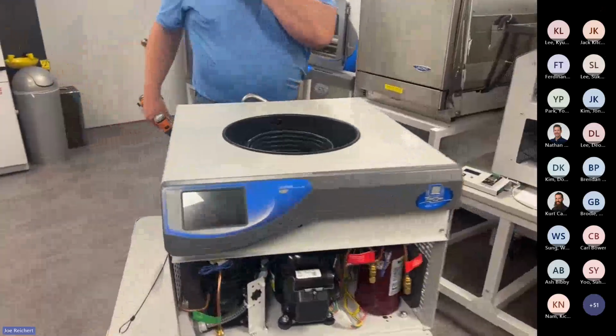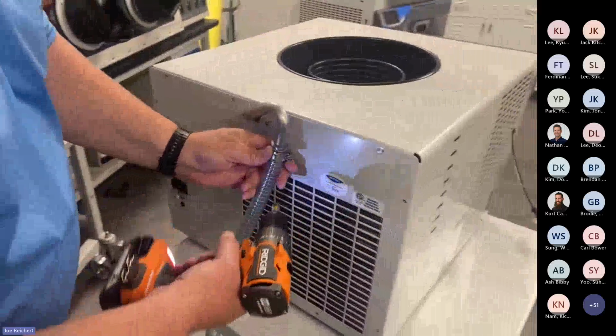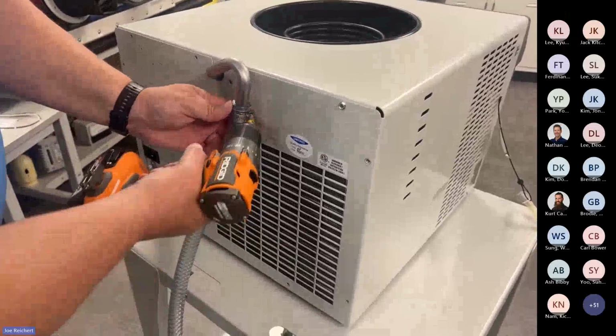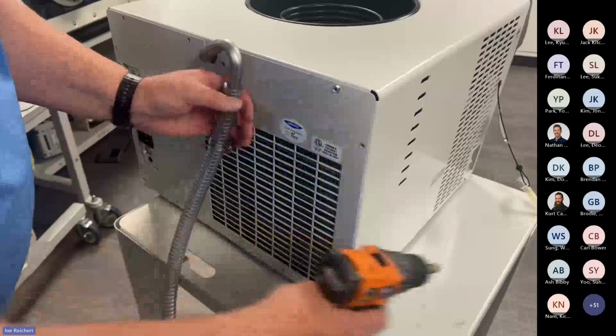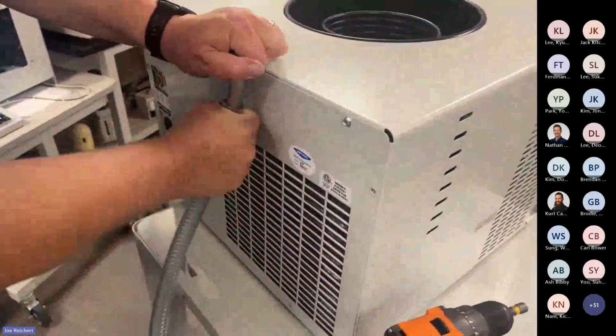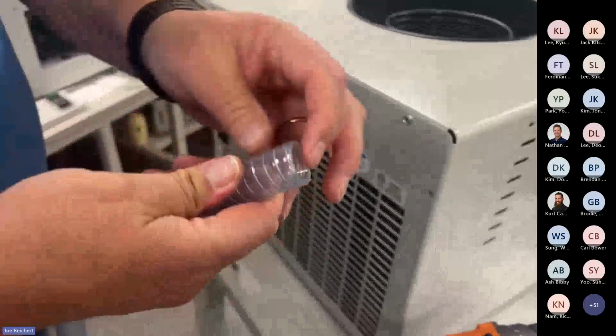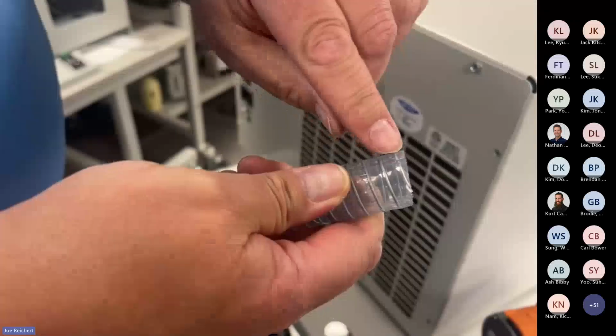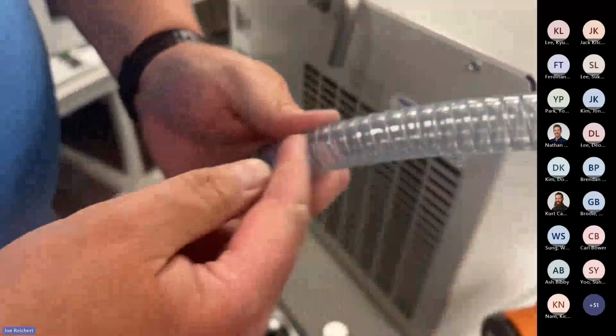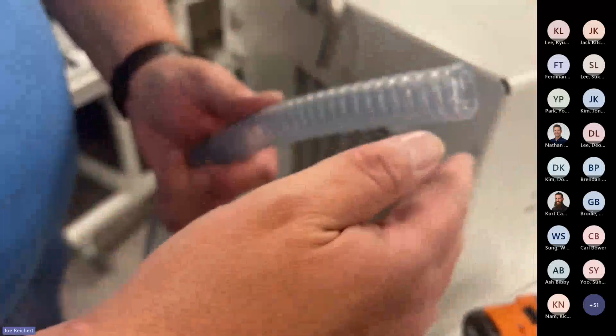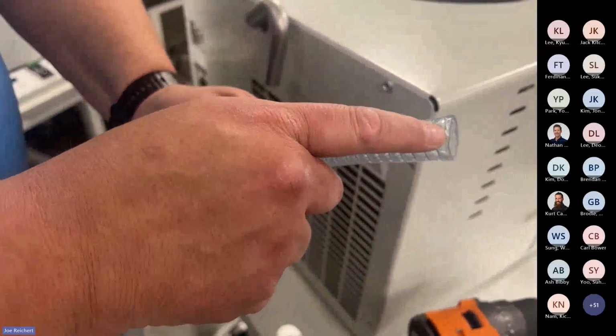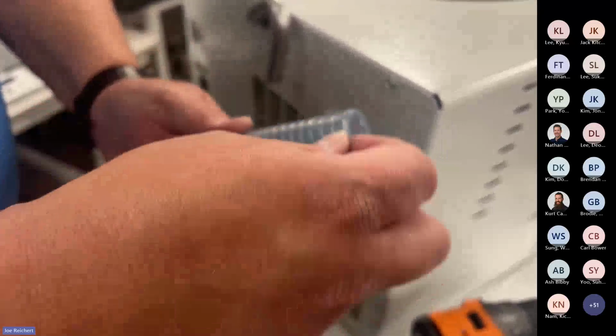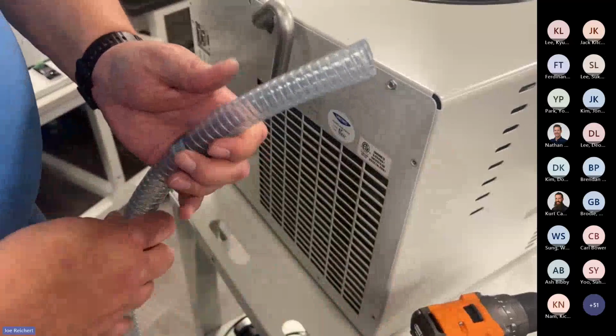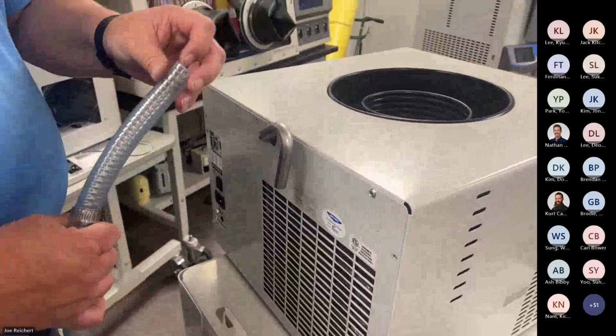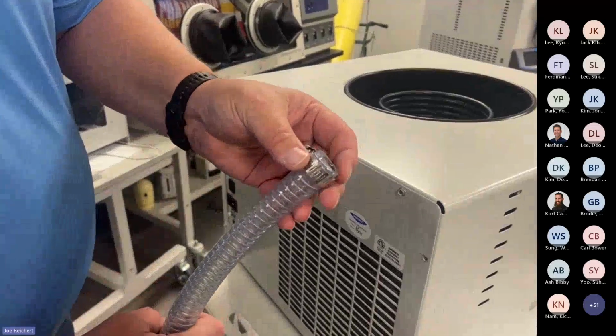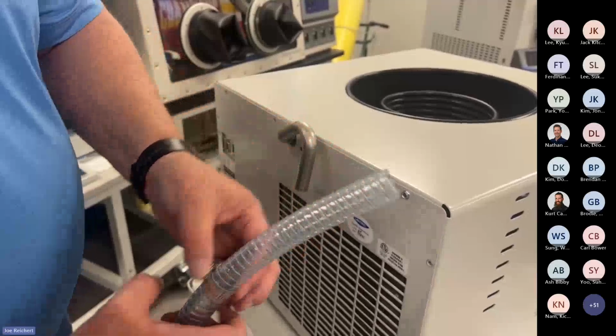On the back of the unit, we have a few more screws. But I also like to point out on your vacuum hoses, you can get a leak at your vacuum hose if you put the clamp right over a slit that we put on these hoses. So you take your hose off. There is a little cut in every one of our hoses on both ends. Sometimes the cut goes deeper, but we try to make it as shallow as we can. Because of the wire reinforcement running through the hose, when we cut the end of the hose, there's always a sharp piece of metal that would be coming out right about there where the wire would come out. So we trim down and then we pull out the piece of wire so that customers and installers and everybody doesn't cut themselves on just the piece of hose. So when you clamp, you just don't want to be at the very end of the hose. You want to be backed off of it just a little bit. You'll be fine.